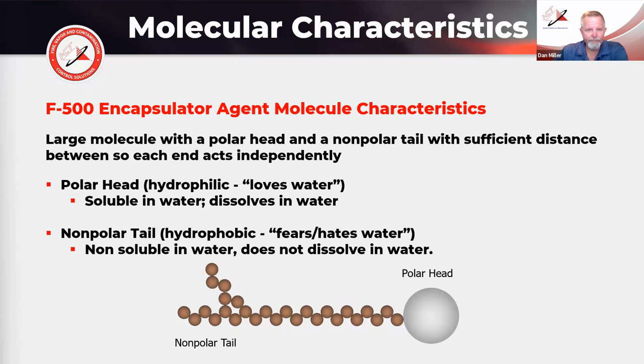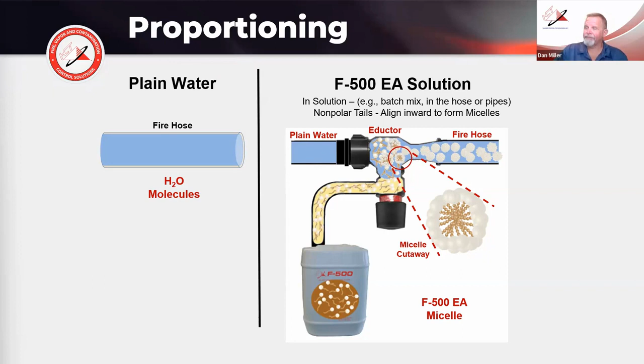With an F500 solution, either batch mixed or in the hose through an eductor or through what we call a water-driven proportioner, as those molecules interface with water, they flip inward, and the tails form on the inside of the spherical micelle. During that process is partially where it does some of the encapsulation. Then as it strikes fuels or passes through buoyant fuels in the vapor space, it traps more as more spherical micelles form. Kinetic energy is an important part of that process.